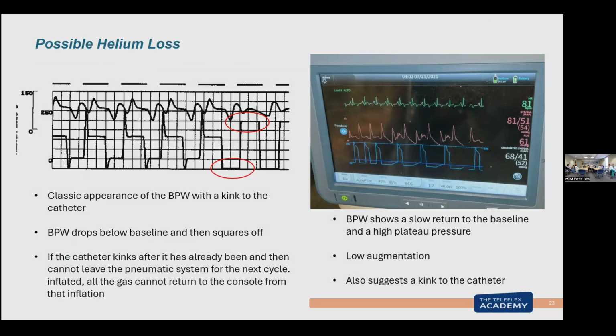So when you have a helium loss, why don't you get back to the baseline? Because the pump says I have to have all that volume back ready for the next beat. If I don't have it all back, something's wrong. If I can't get that helium back to baseline before the next beat, what's wrong? What's preventing me from getting that helium back and forth? Usually a kink.